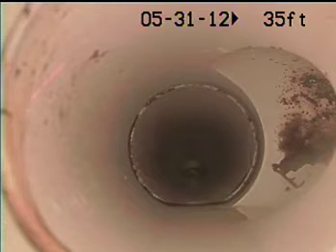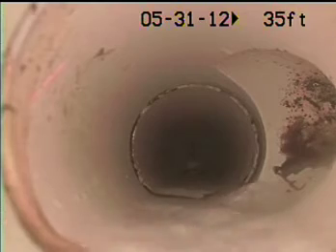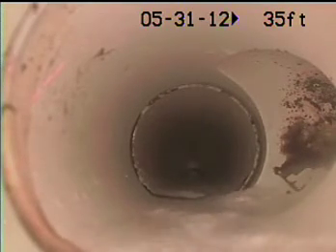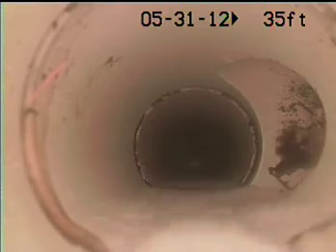No, because it's more elongated. The sweep has got more of an elongation. Looks like it's straight on. Straight in. Yeah, they used a T fitting instead of a Y, which would have been okay if they had canted it up a little bit to get this right down in the flow line. You can almost see where the stuff is stuck to the side of it. That particular room is almost flowing into it, isn't it? It makes me wonder if it's not a Y going the wrong way. No, you'd be able to see up it if it was. Those are real obvious. Go back just another hair. Yeah, the paper and stuff is just catching on that corner. So that would be part of the problem.